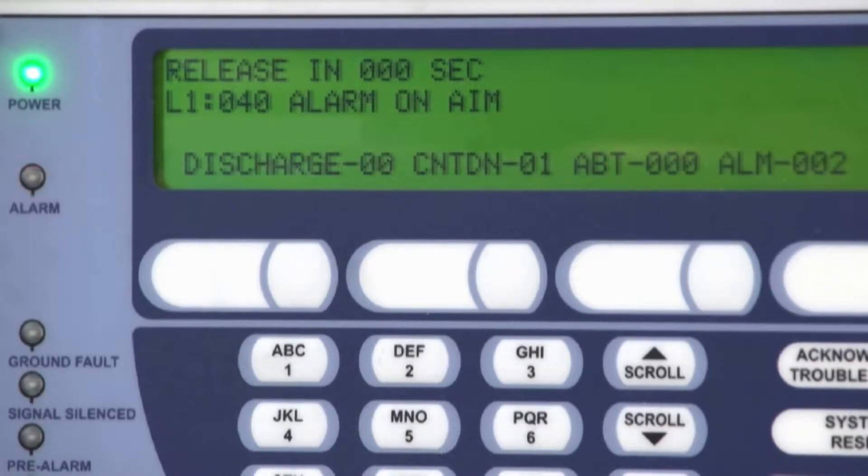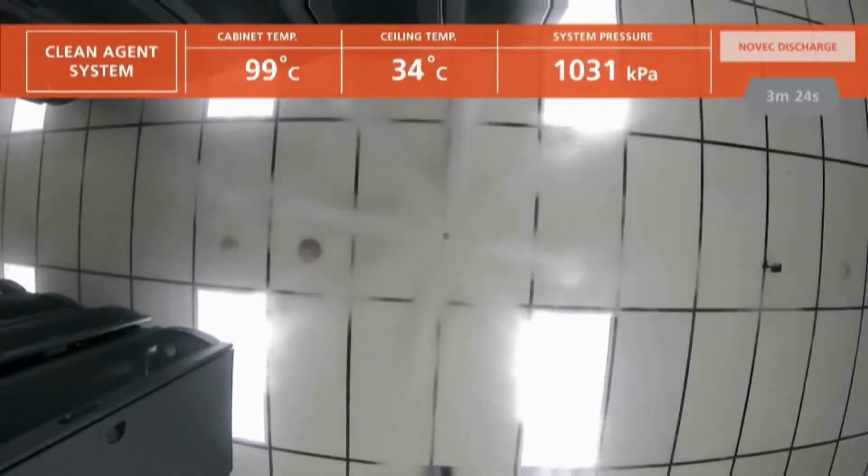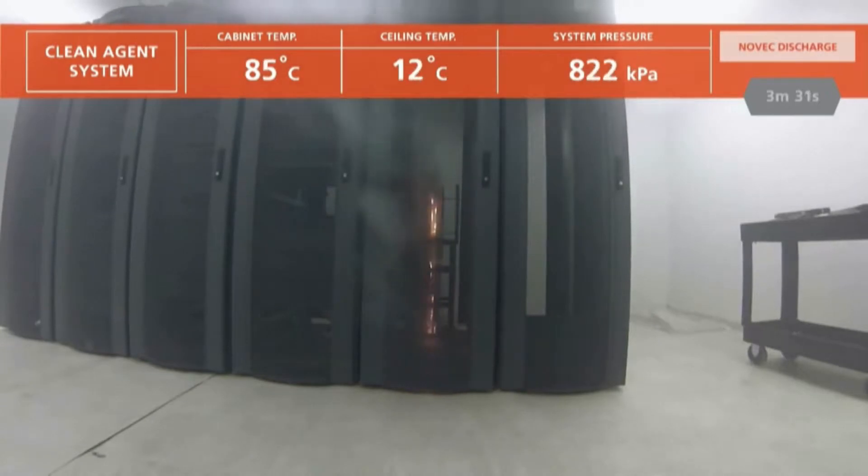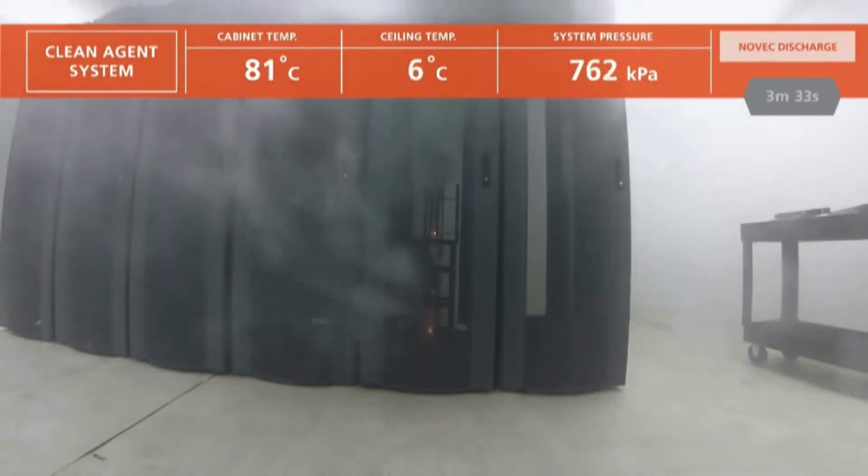And then, discharge. The NOVEC 1230 suppression agent floods the room and penetrates the burning enclosure where it extinguishes the fire in less than 20 seconds.